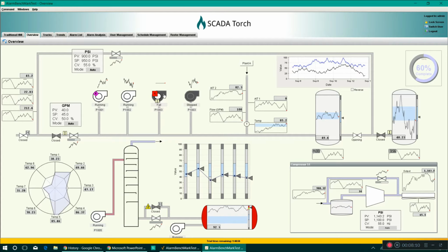The other thing that we need to be aware of when we're designing HMI screens and using color is that color blindness is a real thing, and especially in an industry that's as male dominated as industrial automation, color blindness is dominant in males. There's probably going to be a decent number of workers interacting with this application that have some level of color blindness or maybe are not even aware that they're colorblind.